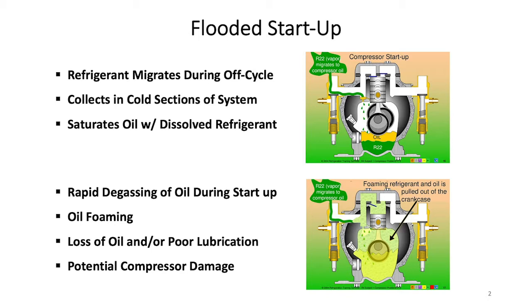A second area of concern occurs when a system is in the off cycle or off season — particularly in winter when an air conditioner is shut down. That's what we call refrigerant migration and flooded start. Refrigerant seeks out the coldest part of the system and can migrate and condense in the compressor sump where it's not supposed to be. It will dissolve into the lubricant, and when the system starts up, a rapid change in temperature and pressure causes that dissolved refrigerant to rapidly degas out, resulting in a lot of foaming. That foam moves lubricant to places where it's not useful, leaving inadequate viscosity and lubrication for moving parts during that flooded start.